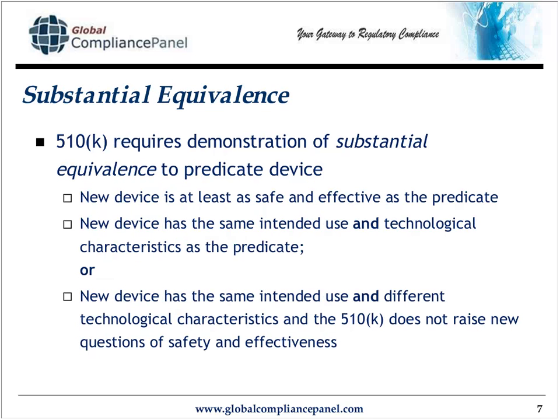Also, you're saying that your device has the same intended use and technological characteristics as the predicate device, or that you have the same intended use and different technological characteristics, but the data you provide in your 510K shows that there's no additional questions of safety and effectiveness. So again, you're providing safety and efficacy data to support your device's clinical use.